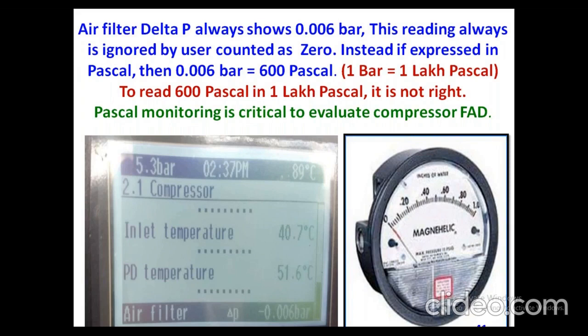Coming to the air intake, we have to educate the textile mill to go for a digital air intake gauge. This one is given by an OEM, and it says 0.006 bar. The textile mill user, as a maintenance person, assumes it is only 0. If you are seeing 0.006 bar, it's 1 lakh Pascal scale. If it is crossing 600 Pascal, this itself is a choke for the FAD. Normally they give 3000 Pascal as the maximum delta P across the air intake filter. If it is crossing 1000, you have to take action to clean the filters. You cannot see 600 Pascal on a 1 lakh Pascal scale.